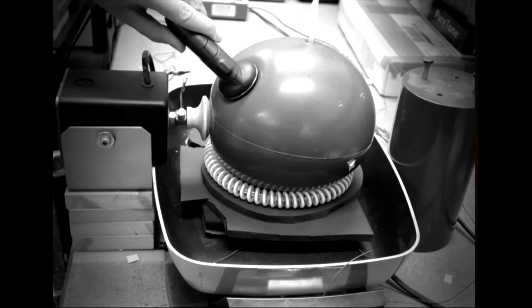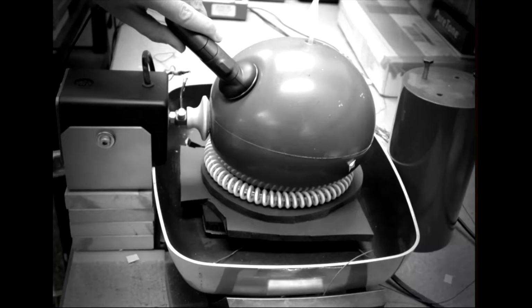I didn't put it in the presentation. It's called the Hello Kitty protocol, because the only balloons we found when we were doing this project were Hello Kitty balloons. And it turns out that if you take a balloon and fill it with water, exactly like this, very sophisticated protocol, put a speaker to one side and a microphone to another side, you can test it. You can figure out how good your stethoscope is.